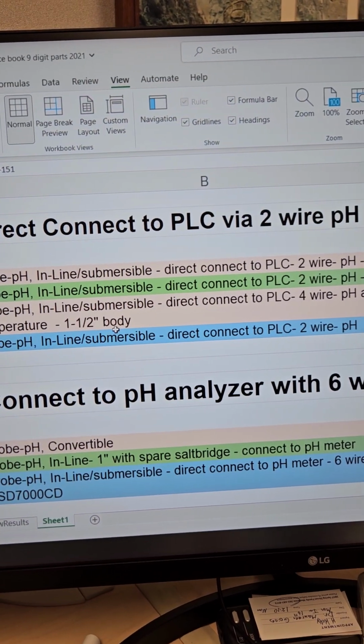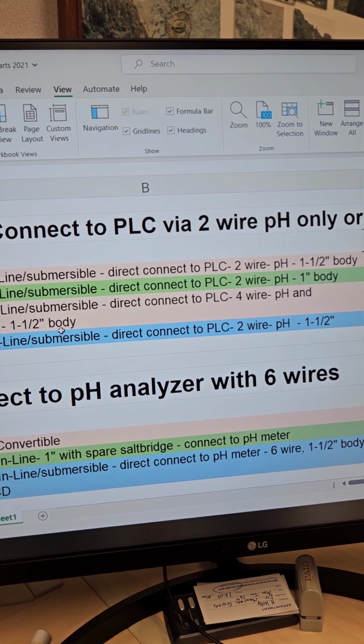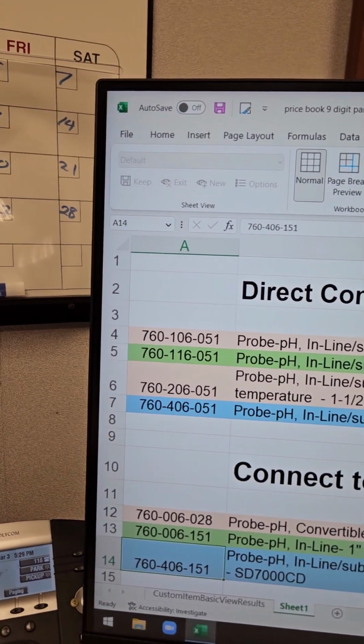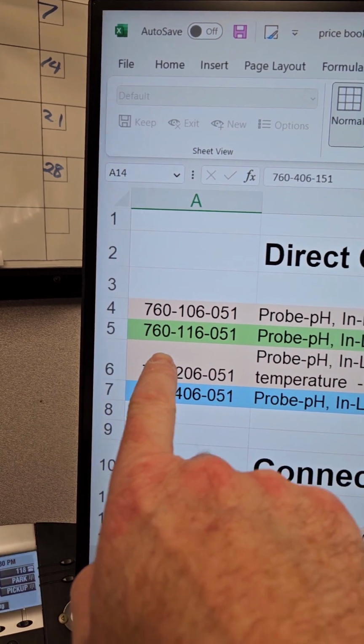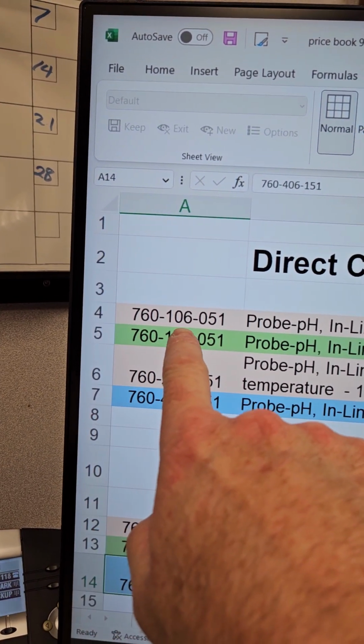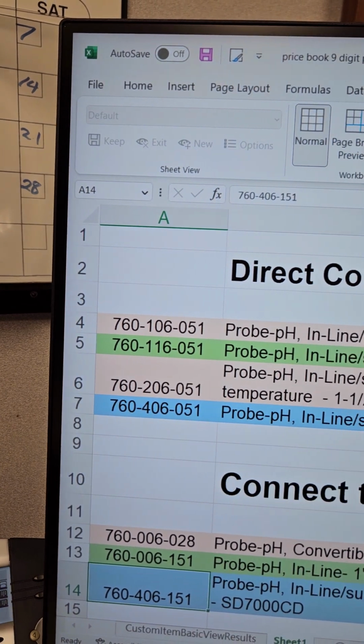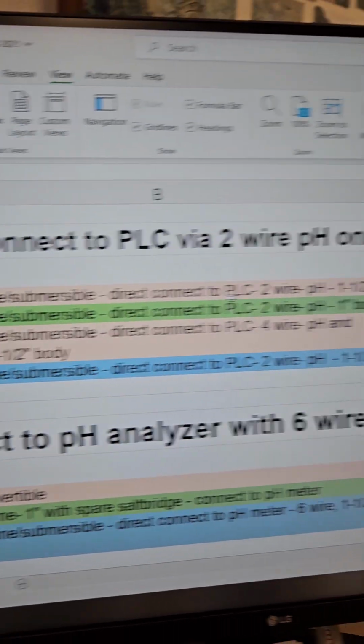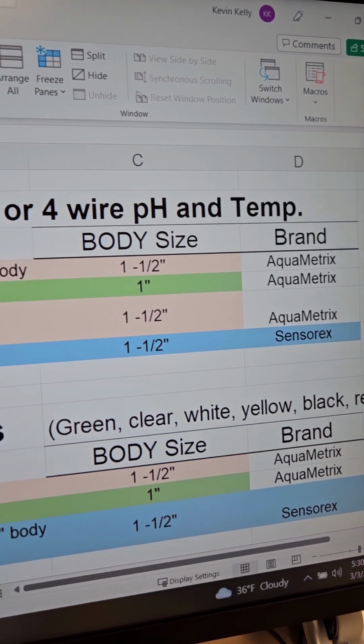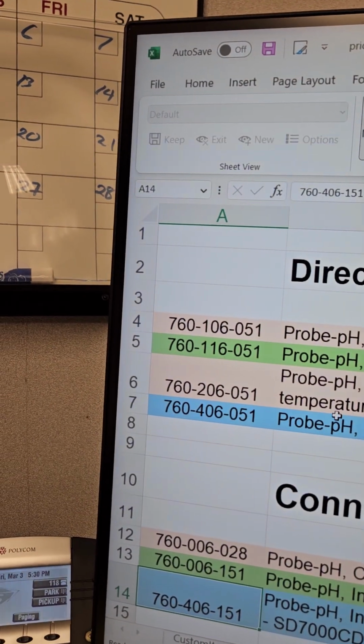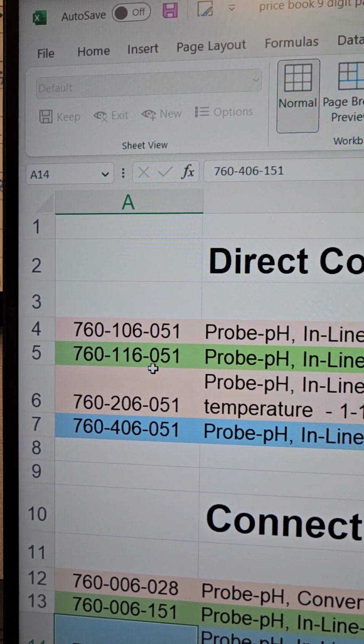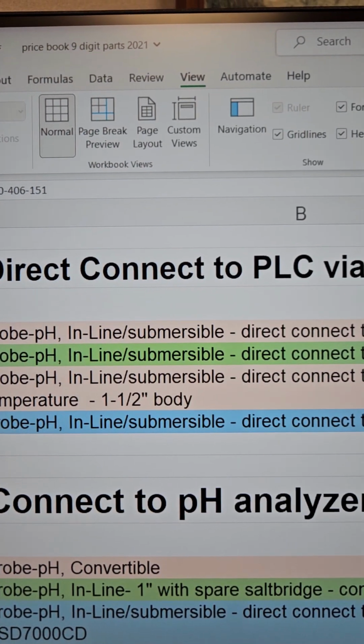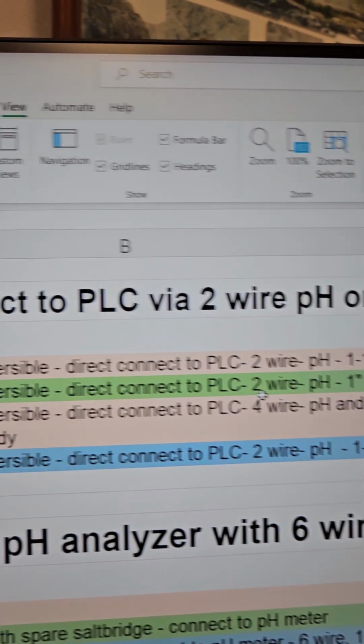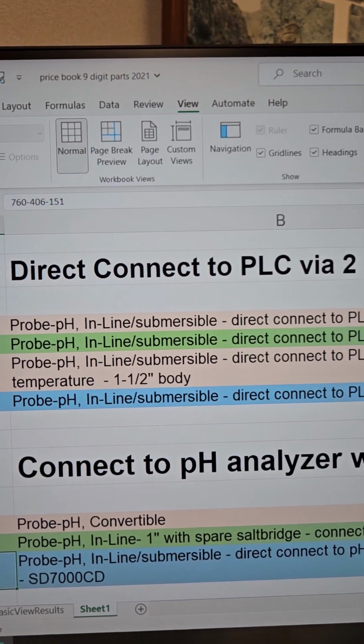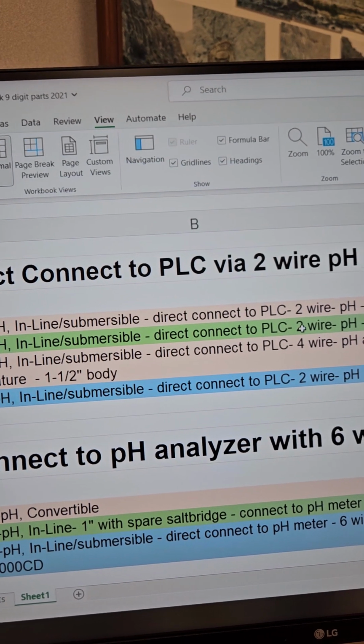We have two different main versions of probes. Direct connect to PLC versus with 2 or 4 wire, and different part numbers. So our 760-106-051 is a 2-wire to PLC with a 1.5-inch body and an AquaMetrix. A 760-116-051 is a 1-inch probe direct to PLC. All of these probes here are direct to a PLC. So if you don't have an analyzer on the panel.